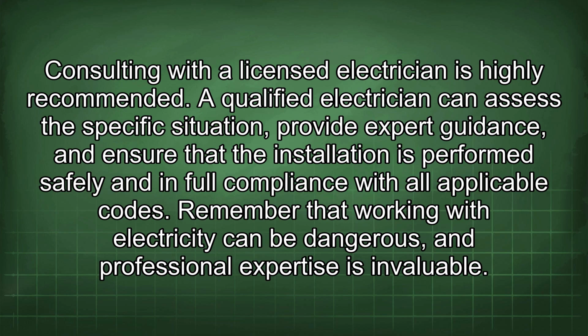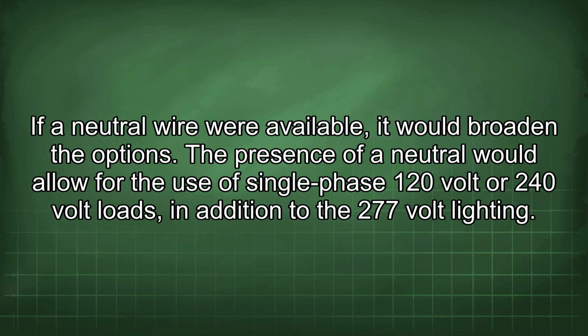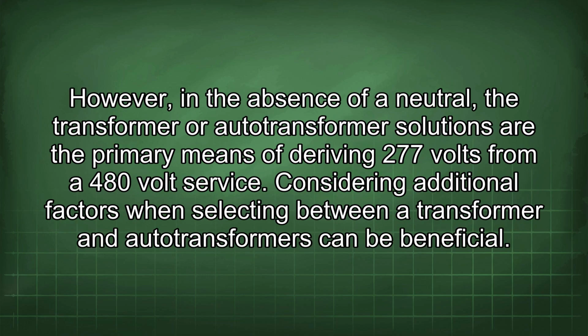Consulting with a licensed electrician is highly recommended. A qualified electrician can assess the specific situation, provide expert guidance, and ensure that the installation is performed safely and in full compliance with all applicable codes. Remember that working with electricity can be dangerous, and professional expertise is invaluable. If a neutral wire were available, it would broaden the options. The presence of a neutral would allow for the use of single-phase 120 volt or 240 volt loads, in addition to the 277 volt lighting. However, in the absence of a neutral, the transformer or autotransformer solutions are the primary means of deriving 277 volts from a 480 volt service.